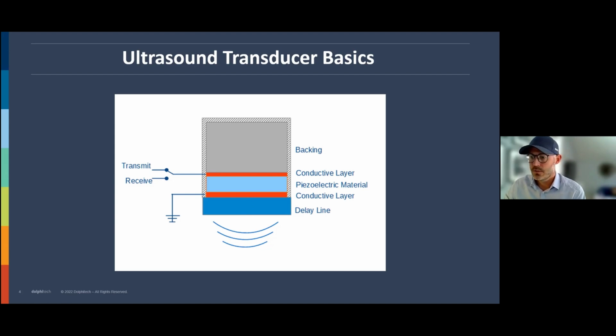So when the sound hits the part that you're inspecting, and then hits the back wall of it or a crack, it goes back through the delay line and into the piezoelectric material. And then again, the piezoelectric material starts to vibrate. In the meantime, you will have the switch here turned from transmit to receive. And this vibration in the piezoelectric material creates a small, tiny charge on the top conductive layer. And this is what you use to make your signal that you're using to inspect.